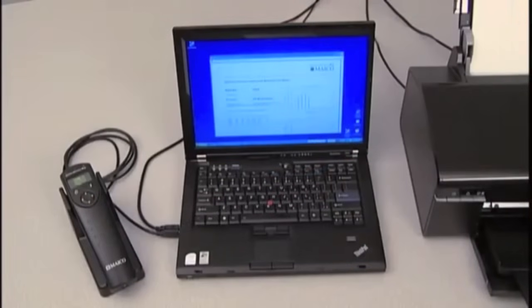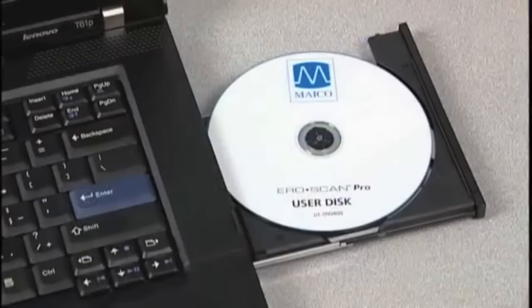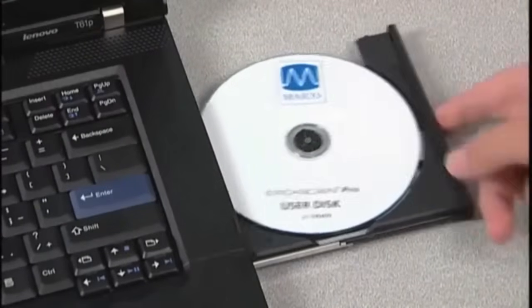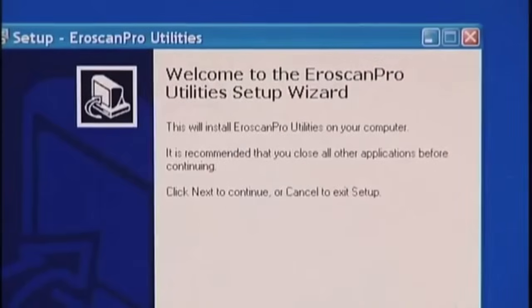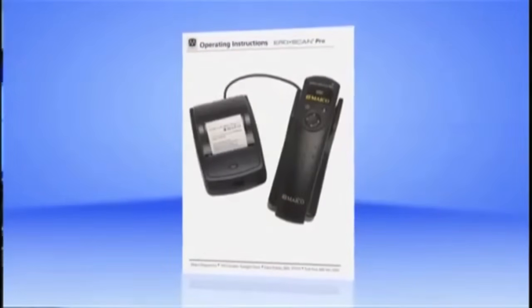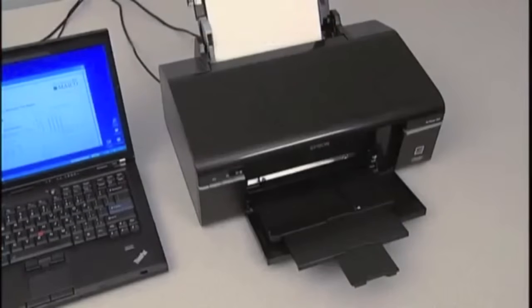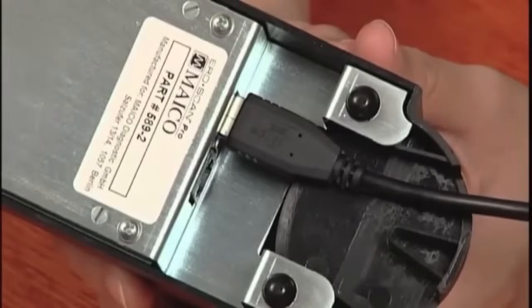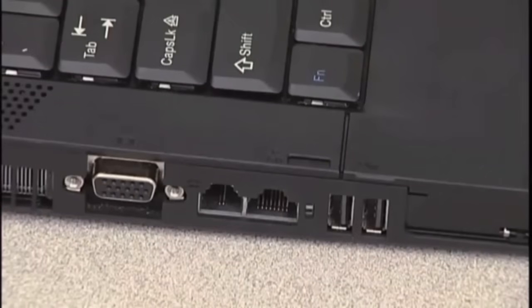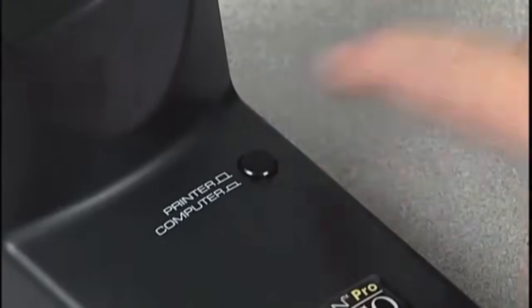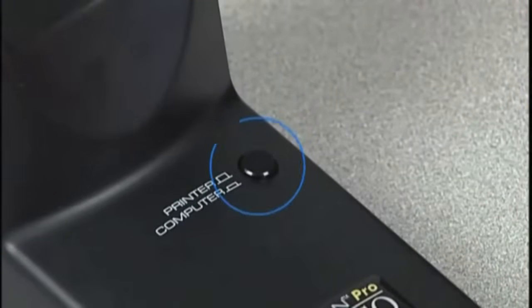First, let's cover connecting the Ero Scan Pro to your computer. Begin by inserting the software CD into your computer and following the prompts to install the software and drivers. Detailed instructions can also be found in the operating manual. To print to your computer's default printer, connect the supplied USB cable to the USB connector on the cradle and then to your computer. These connections are designed to fit in only one direction. Once the connections are made, make sure that the button on the cradle is in the depressed position. This routes the cradle output to the computer connection.